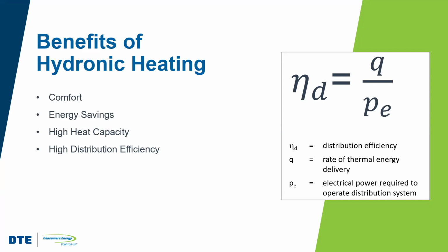So basically, for your hydronic system, it's looking at the amount of heat that you're putting out compared to the pump energy that you're expending, or that's required to get that heat where it needs to be. And that pump energy is based on the volume of water, the length of the piping, the fittings that are in the piping, the height of the piping, and the location of the radiators. All of that goes into developing the power requirement for those pumps.